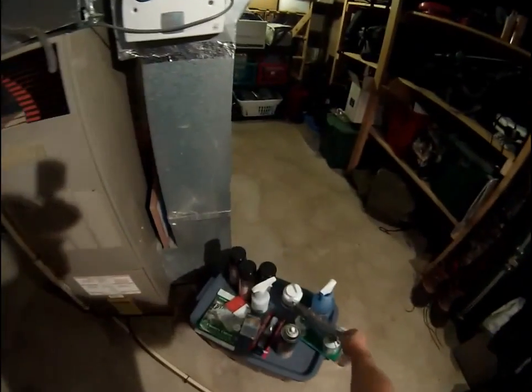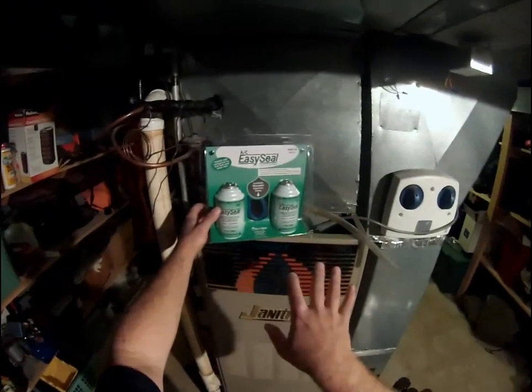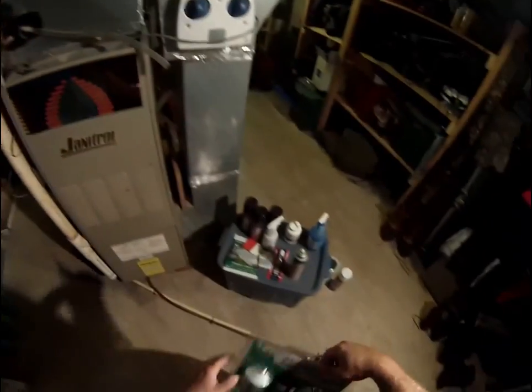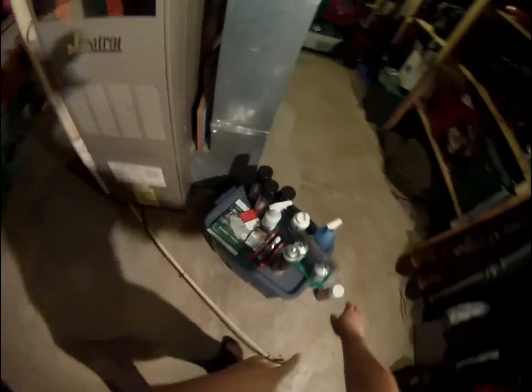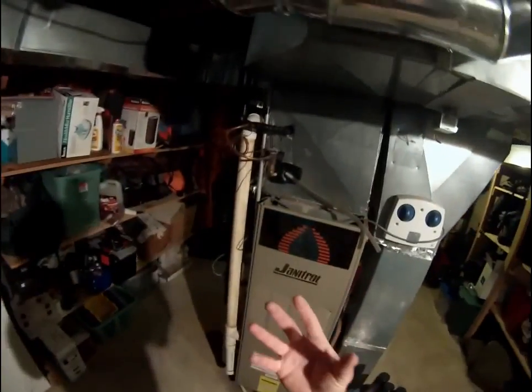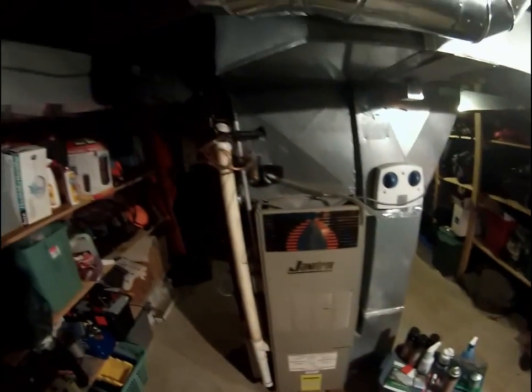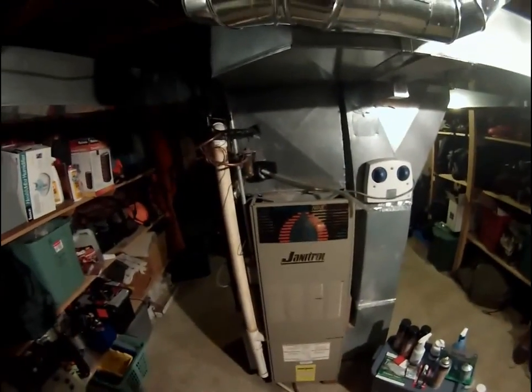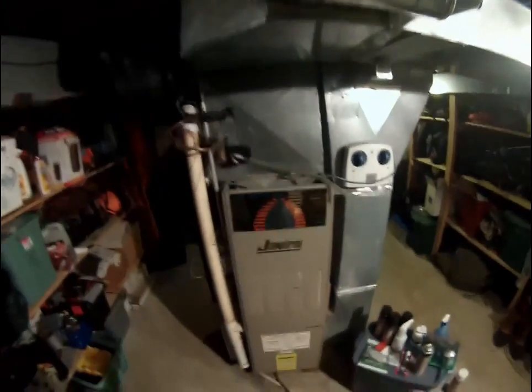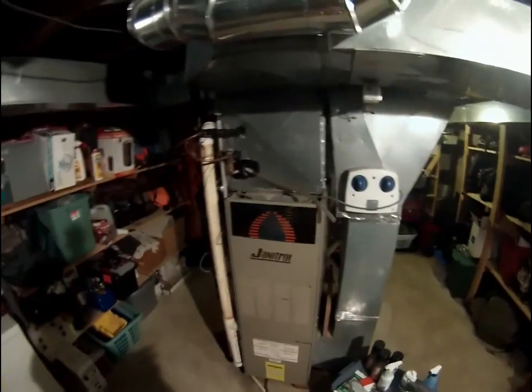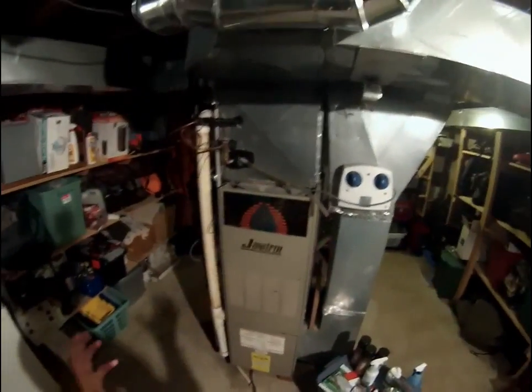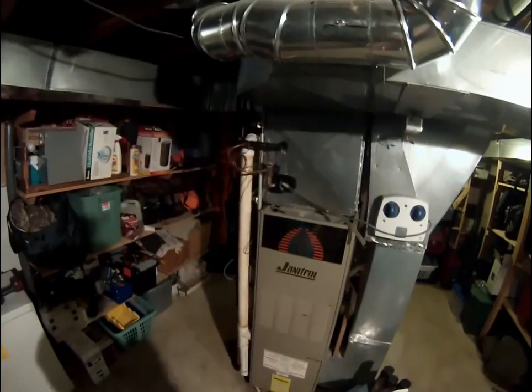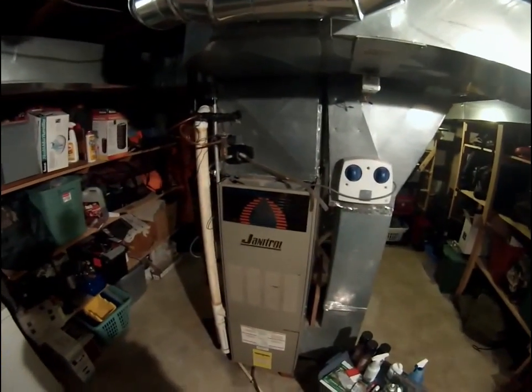Another option out on the market, and we have this product available on our site as well, is AC Easy Seal. It's a great product. You can look at some of our other videos on that as well. You can put it into the system, and it'll go out and seek the leaks and seal them up. Works real well on smaller leaks. And then of course you've got to get it charged back up, and a technician comes out and charges it to the exact superheat or subcooling and gets you set back up.